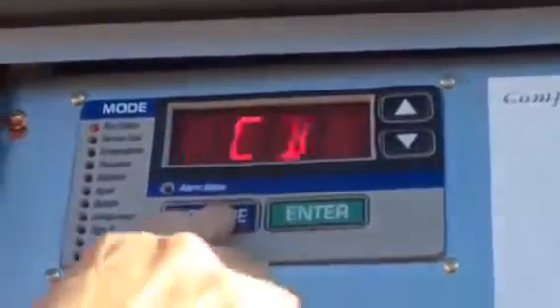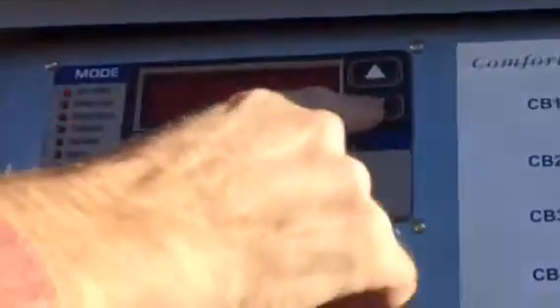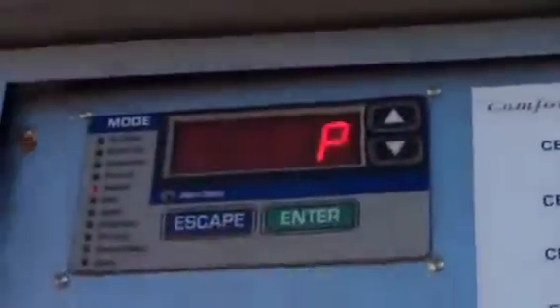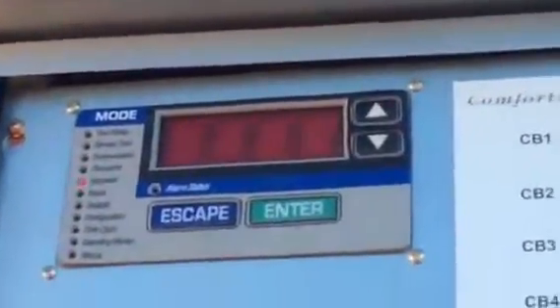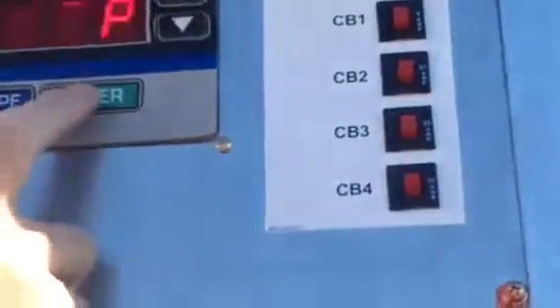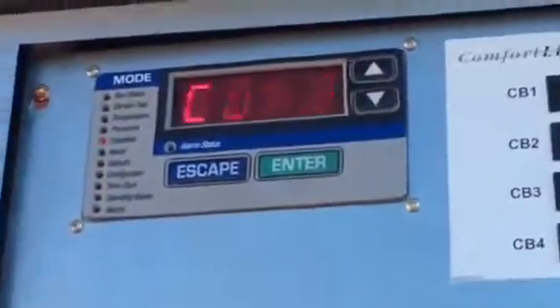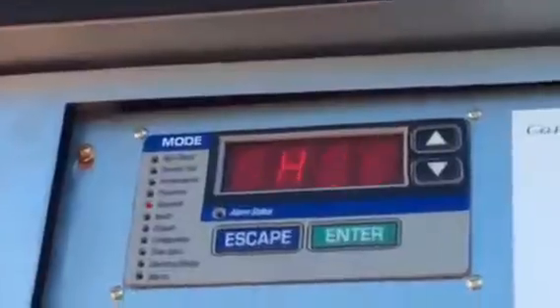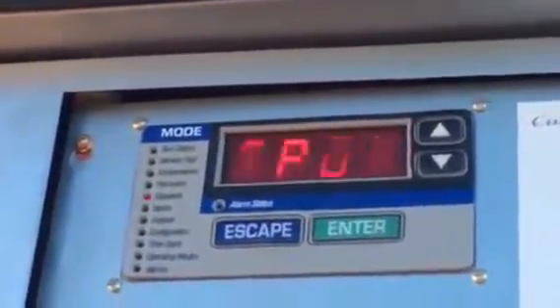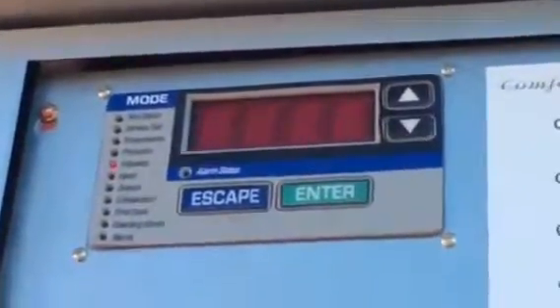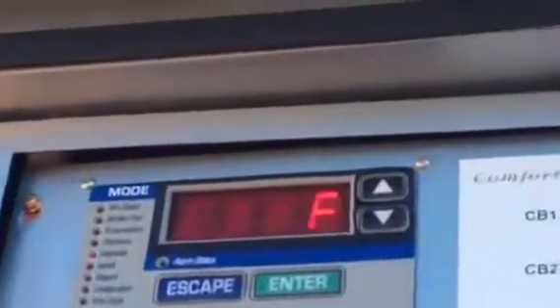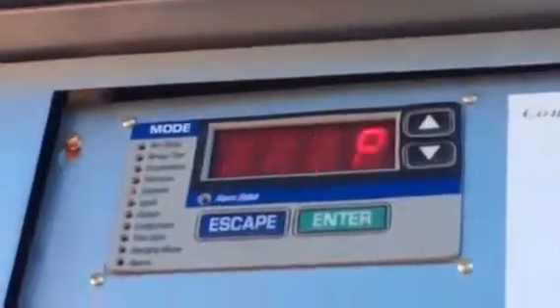I can call up set points, escape twice till it goes blank. I can look at temperatures, pressures, or set points. What is OHSP? We escape and enter heat. Some with the outside heating set point. Occupied. That's my occupied heating set point. And a VAV unit bases its decisions off of that. Even though this is a straight cool unit, the fact that I'm in VAV mode, that's where I start things.